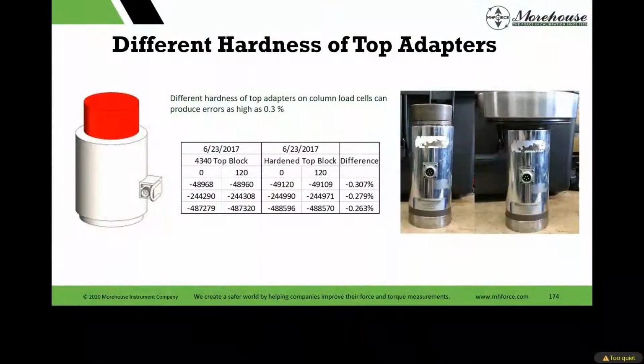Take note, whether you're field, reference, whatever, these top adapters that are used with the majority of load cells, not all of them, can impact the results significantly, because different amounts of hardness, and I'll show that in a slide, are going to affect the strain on the load cell. And here's a test that I did. This is the reds, obviously the top adapter. I had this cell for like a week. 4340, that's a steel, hardened top block, and it wasn't super hard. Sometimes people ask, maybe like an RC of 42.